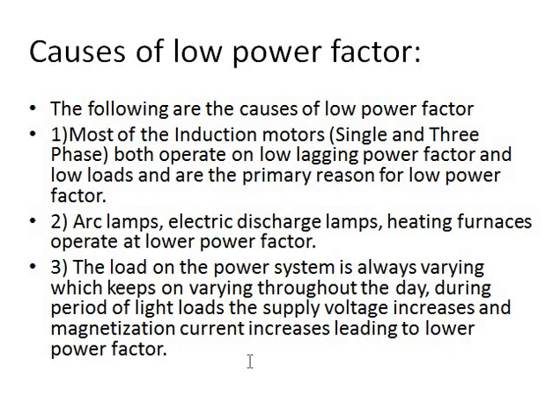Now, what are some of the causes of low power factor? They may be making use of inductive load on a very high scale. That may be one of the primary reasons. Like most today, we know, 90%, 95% of the machines which are used are induction based. So most of the induction motors, single and three phase, both operate on a lagging power factor, and if they are operating at low loads, they are the primary reason for low power factor.